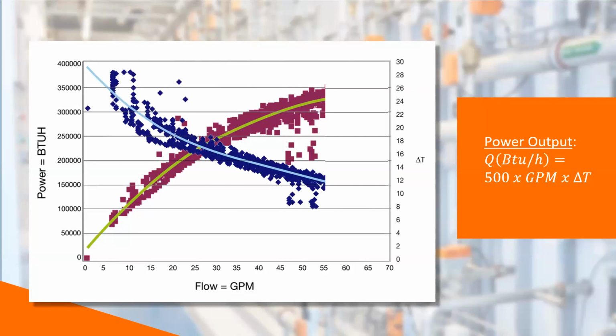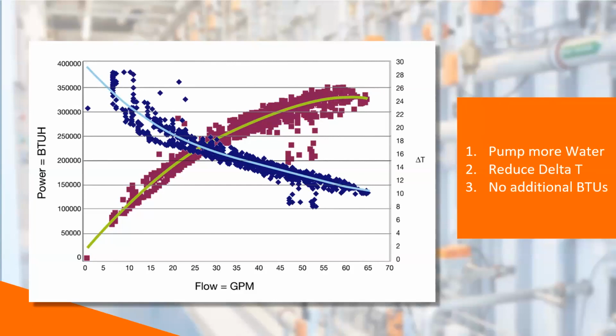What happens when the coil receives more than 100% of its design flow, or its saturation point? Well, there are 3 penalties for overflowing. We're pumping more water, we're reducing the delta Ts, and we're not producing any additional BTUs, or minimal BTUs. So what we mean by not producing any additional BTUs is that the discharge air temperature and room temperature won't change at the same rate as before the overflow. And really, with traditional control valves, there's no way to detect that overflow through measuring just the air temperatures.